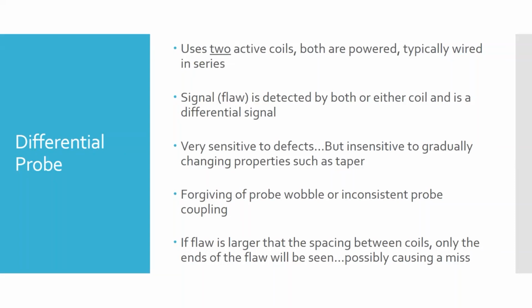The nice part though is these are more forgiving. When you use an absolute probe, any little wobble shows up as an indication - that little pointer moves around the screen. When you use a differential probe, you don't get as much noise in your signal from a little bit of wobble or unsteadiness. So they're good for that.